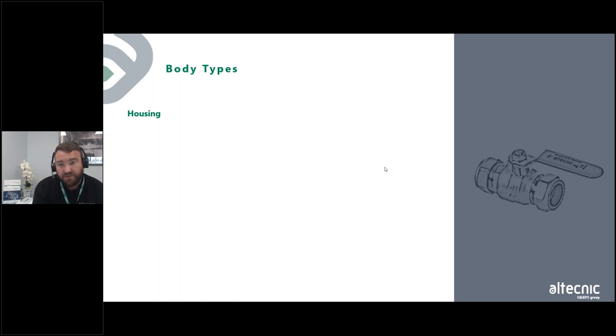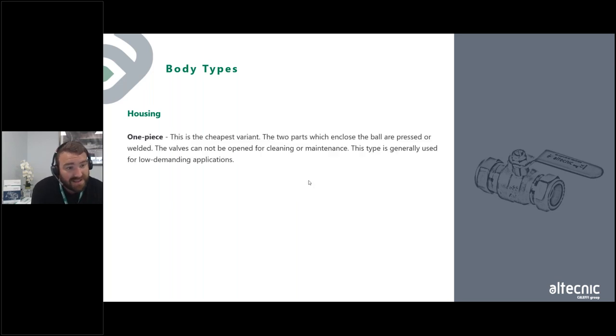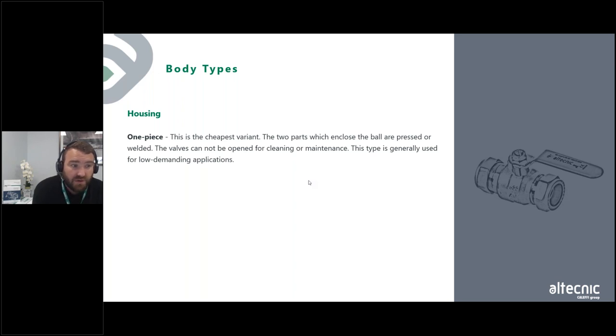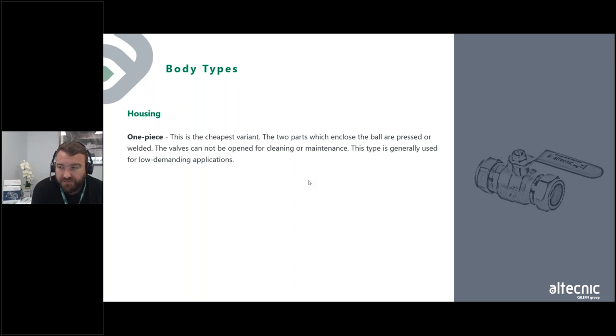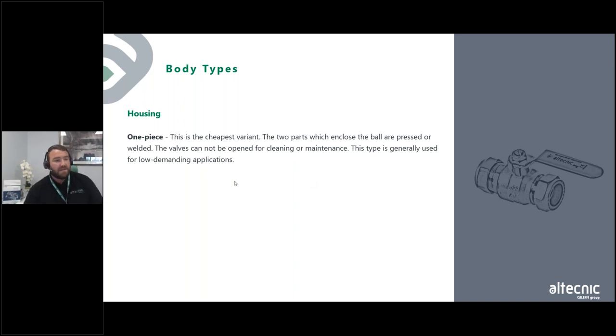There are different body types for ball valves. A one-piece ball valve is the cheapest variant — the two parts that enclose the ball are pressed or welded together. The valve cannot be opened for cleaning or maintenance and is generally used for low-demand applications. It's an entry-level valve, not suited to very high temperatures or high pressures.